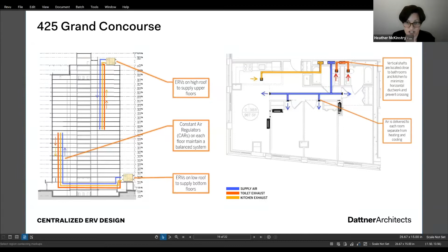All of this equipment is really standard and easily available these days. One area where we weren't able to go all electric was domestic hot water heaters. In 2018 and 2019, when we were finishing design, there wasn't an electric hot water heater that could serve a building of this size on the market, so here we do have gas for domestic hot water. But that market has completely changed in the last couple of years, and now that those units are available, we're doing electric hot water heaters in buildings where developers want to limit their reliance on gas service, whether or not they're trying to build to passive house standards.